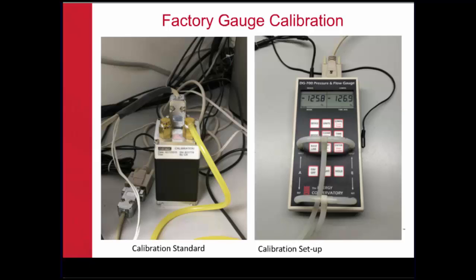This is our factory calibration setup. So on the left-hand side, you can see a Mensor device. That is a calibration standard. You can see the pressure tube attached to the right-hand side. So we're applying pressure. We're also applying that same pressure to the gauge that you can see on the right-hand side. And we compare the Mensor calibration device on the left with the values of the gauge on the right. Now we don't do it by eye, we do it through the computer, and you can see the computer connection right up on top.